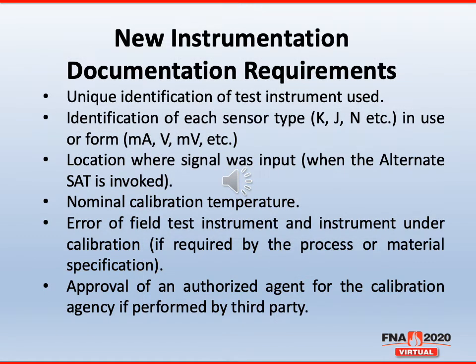There are now some new added documentation requirements when it comes to the calibration of process instrumentation. First off, you have to have a unique identification of the test instrument used. So if you have an asset ID number associated with a test instrument used to calibrate the equipment, that's just going to have to be denoted on your calibration documentation. You also have to identify each sensor that may be calibrated or signal that would be calibrated. For instance, you have a vacuum furnace that has a type S control and over temp thermocouple, and there are type K load thermocouples inside the furnace. You're going to have to denote that the control sensor and over temperature are type S, as well as the load thermocouples are type K.